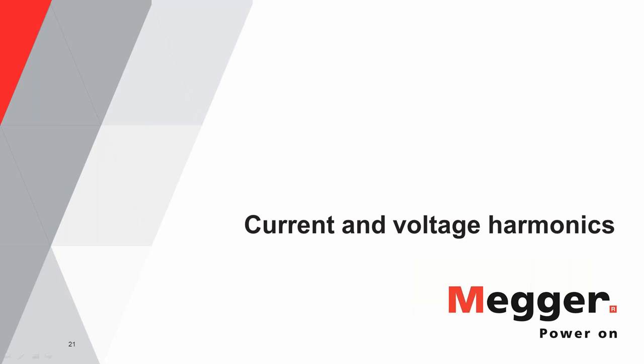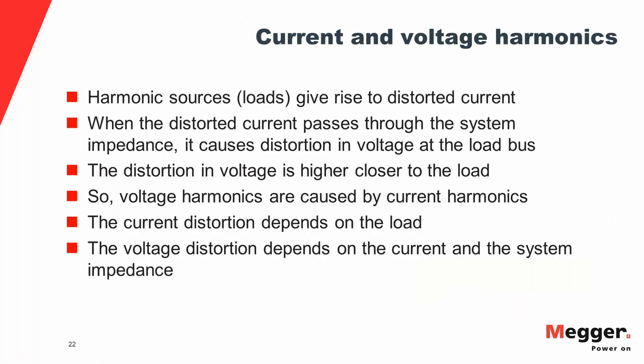Moving to current and voltage harmonics: current harmonics are the distorted current drawn by nonlinear loads. When that distorted current flows through the system impedance, it gives rise to voltage distortion. Current distortion depends solely on the load, but voltage distortion depends on both the current and the system impedance through which it passes. Voltage harmonics are therefore caused by current harmonics.